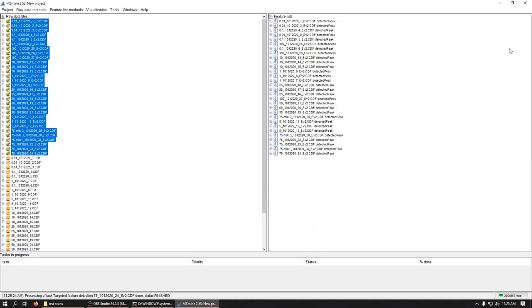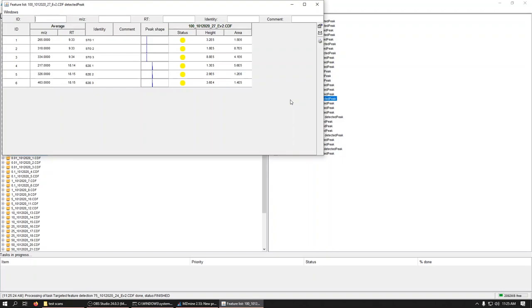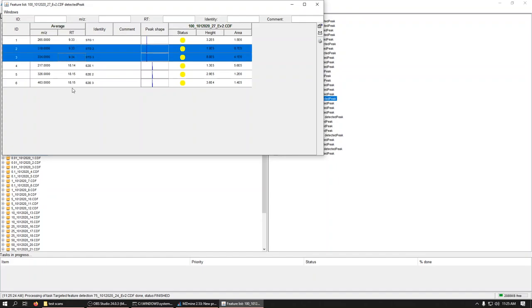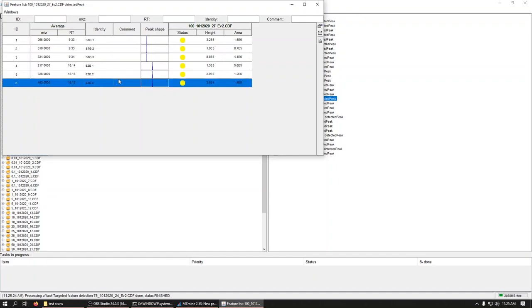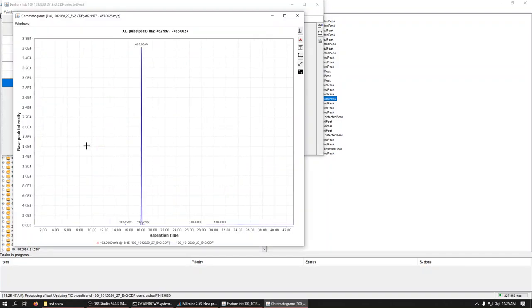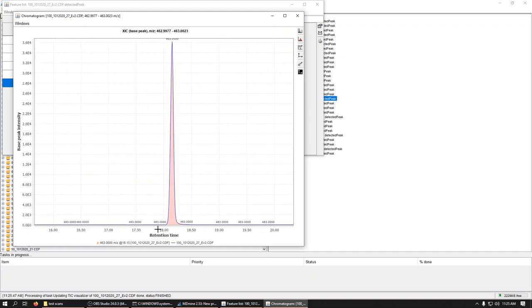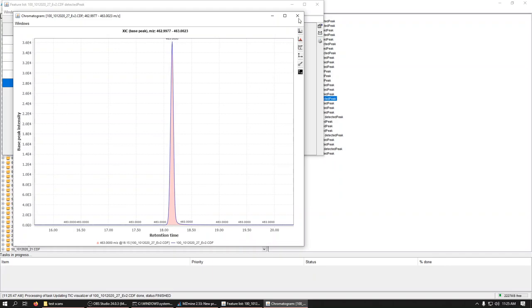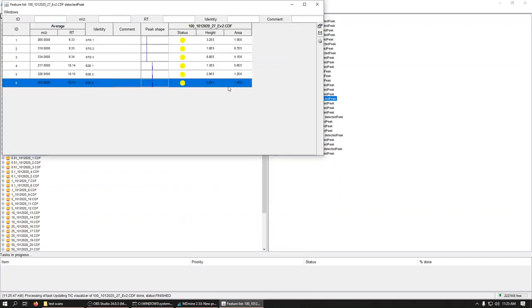And again, it'll chew through it. And now we've got our feature list. So if we pick one of these, you can see here it went and found a single ion chromatogram for each mass we gave it. Calculated the center retention time. And it integrated a peak. So if we right click and show extracted ion chromatogram. There we go. We can see this peak that was quantified. And our pink shows us this is the area that was integrated by the program for us.